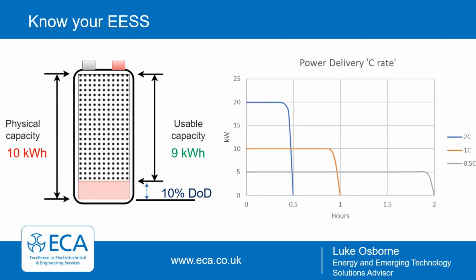For example, on your screen here there are two different diagrams. On the left-hand side you've got a depiction of the battery, so it's important to know what you're being told by the manufacturer. For example, this battery here has a physical capacity of 10 kilowatt hours - it can hold 10 kilowatt hours, but it can't discharge that whole amount of energy. Inherently, especially lithium-ion batteries, they can only go down to a depth of discharge of about 10-20%, depending on the manufacturer. So in this example there's only 9 kilowatt hours of available energy to use.